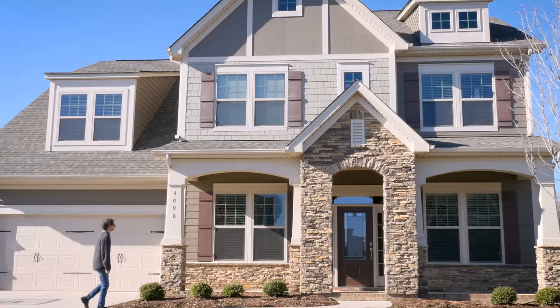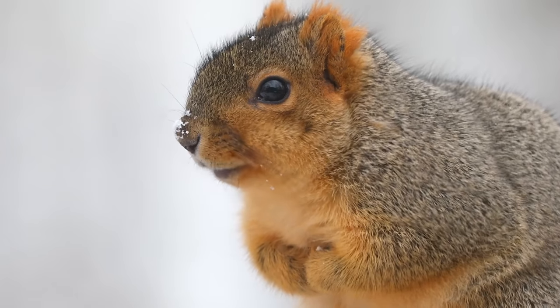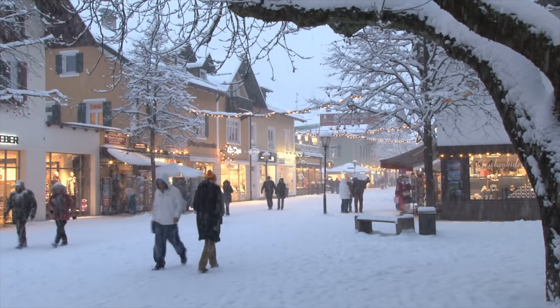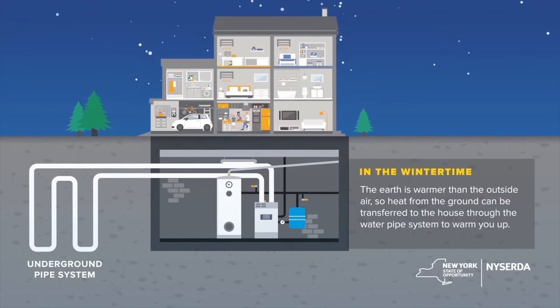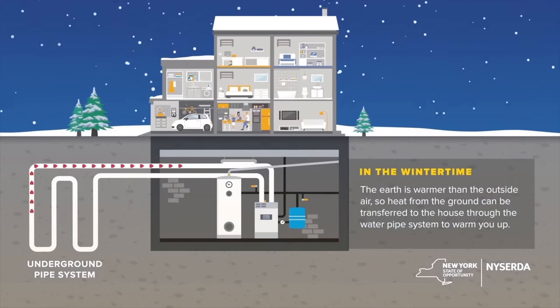This is where geothermal heat pumps really begin to shine. No matter how wildly the air temperatures might vary, underground temperatures are always going to be pretty consistent between 50 and 55 degrees Fahrenheit. No matter how grueling the winter gets, the geothermal heat pump will almost always work at its maximum efficiency. Geothermal heat pump COPs can range between 300 and 600%, making them significantly more efficient than gas or electric, and at the worst, comparable to air source heat pumps. When temperatures outside are moderate, air source and ground source are not too different — but on a scorching hot day running your air conditioner or a freezing cold day needing heat, that's where geothermal really shines.